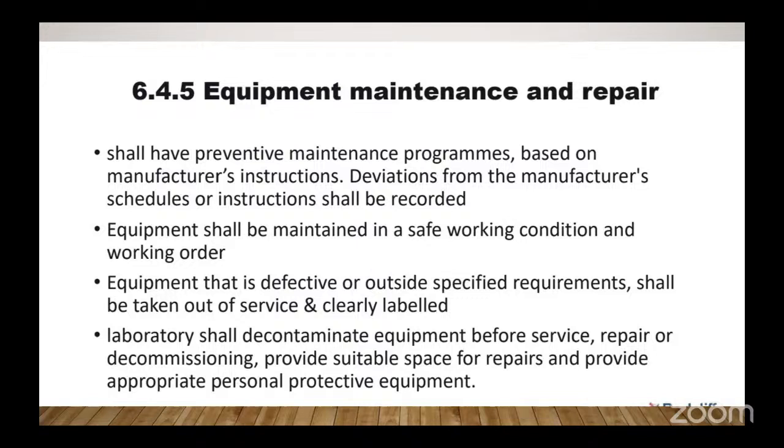So you have to maintain. So there must be a schedule for your periodic maintenance, for your preventive maintenance. And if possible, there are some of these preventive maintenance items where you will need to order the parts, maybe from outside the country, from Europe and so on. So you must create avenues for that. There are some equipment that, once they have done some number of tests, have to undergo some maintenance. So all these things have to be in place, and there must be proof, documented procedures of your daily maintenance, your weekly maintenance, monthly maintenance, and your preventive maintenance.